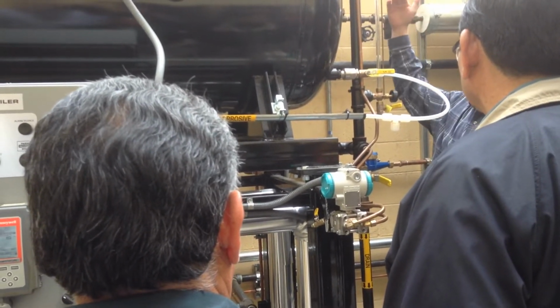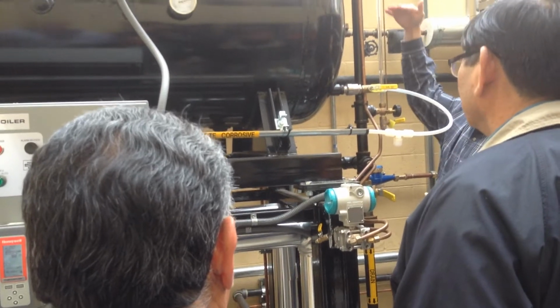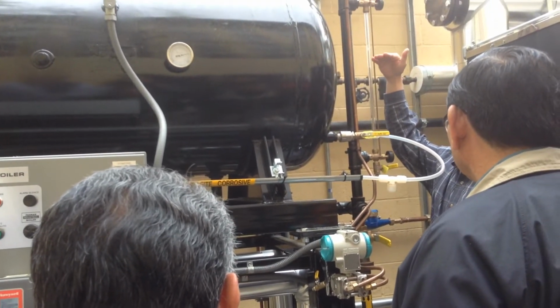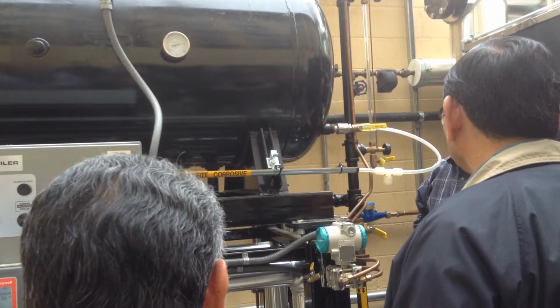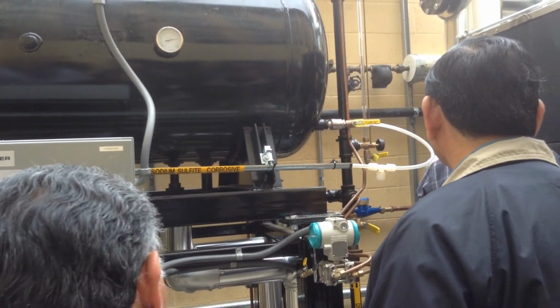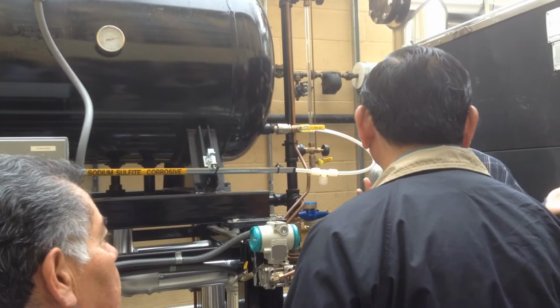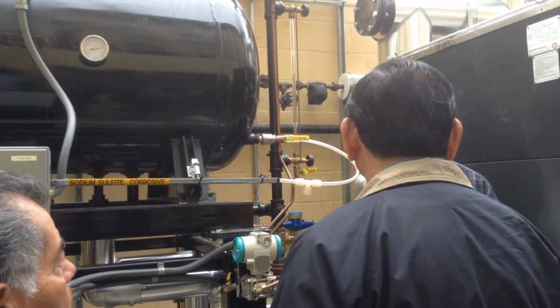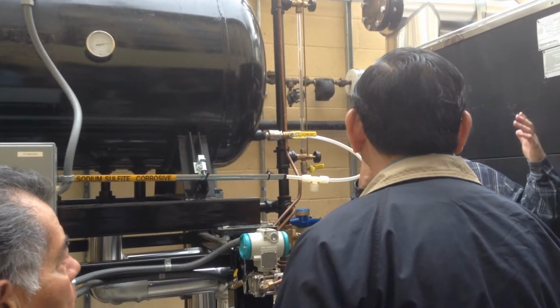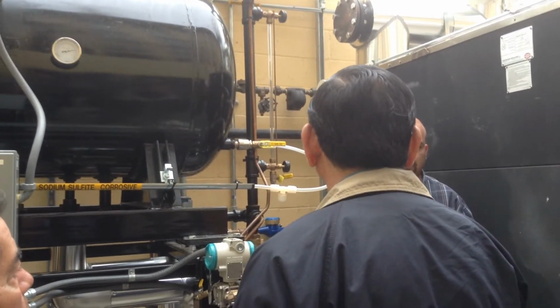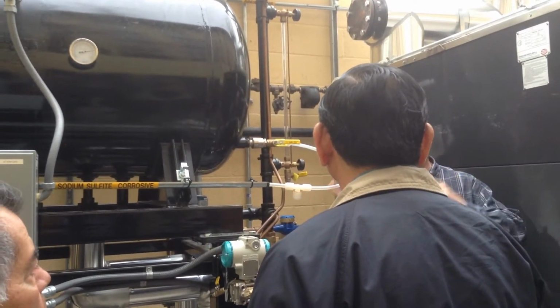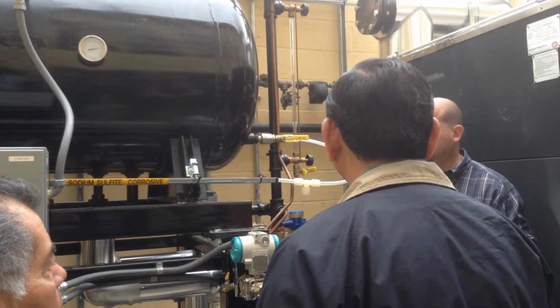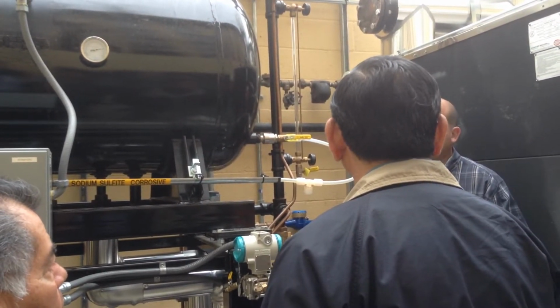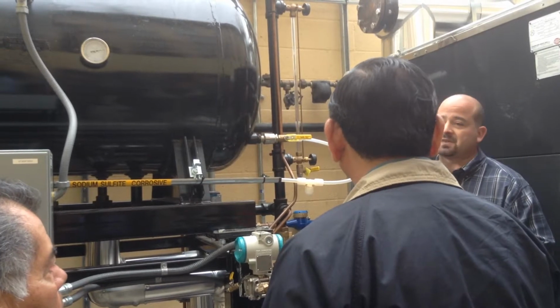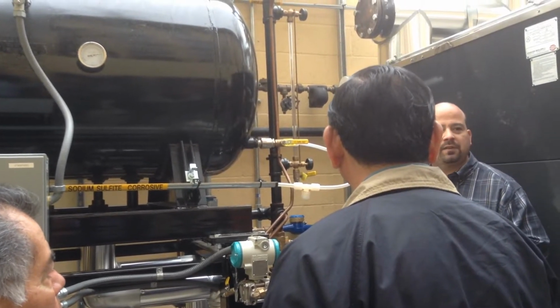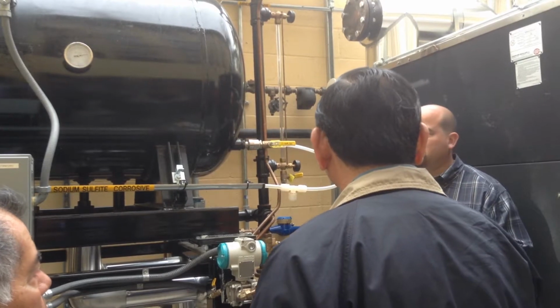When the water level is at its normal level, which is typically about 50% of the tank, it'll be closed all the way. My guess on this system is that because theoretically this is pretty much a closed loop system, you're not bringing in a whole lot of fresh water. It's pretty much just steam goes out, heats the radiators, turns into condensate, goes to the condensate transfer unit, gets pumped back to the deaerator. You're not really going to be taking out a lot of fresh water, so I don't expect this to be cycling much. Other than evaporation losses, but very minimal.